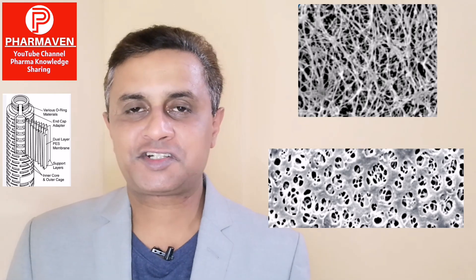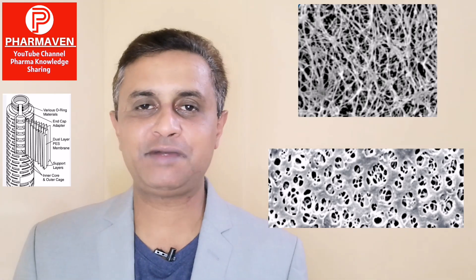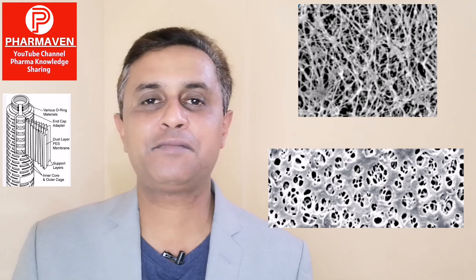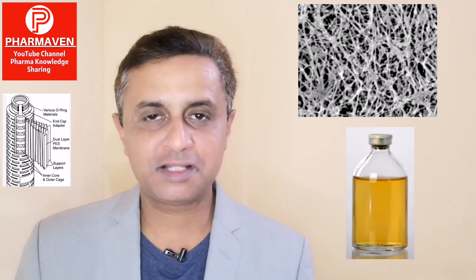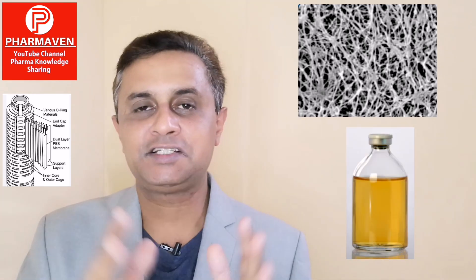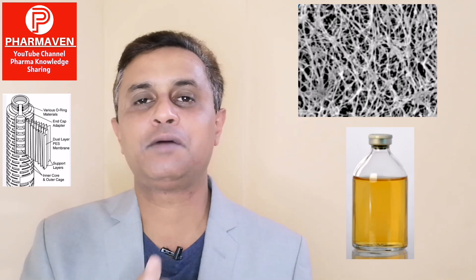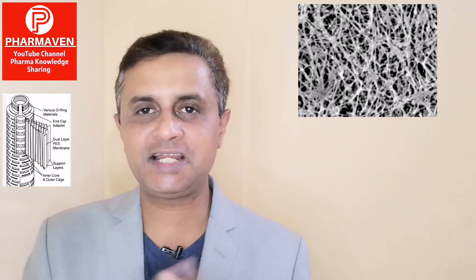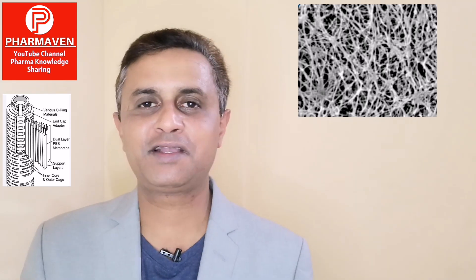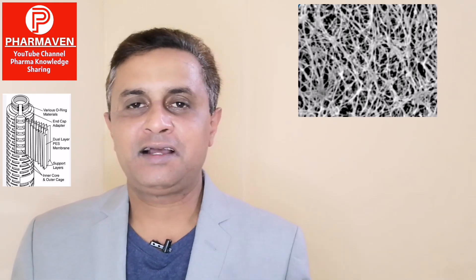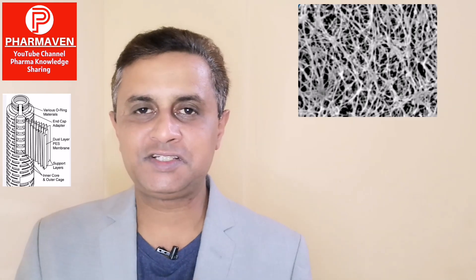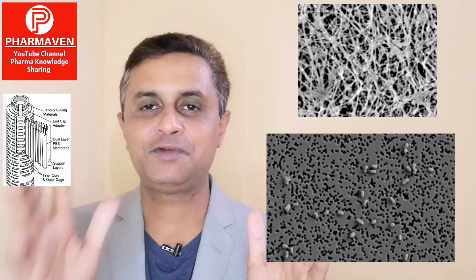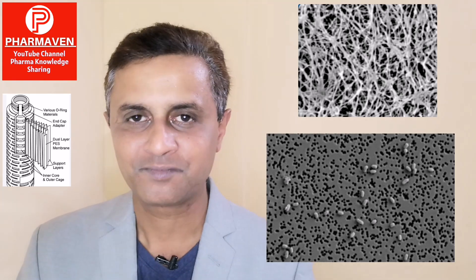This complex structure physically retains the microorganisms. It is mostly not impacted by the number of microorganisms within the liquid; however, it is impacted by the composition of the liquid, filtration conditions, and temperature. Practically, it is simple physics: microorganisms larger than the pore size of the filter will get physically retained by the filter. It is not impacted by the number of microorganisms within the solution.